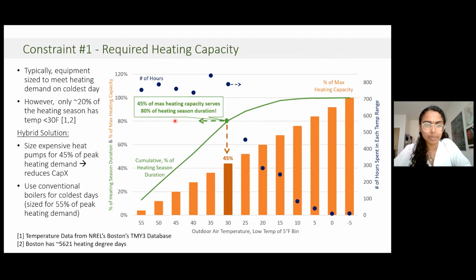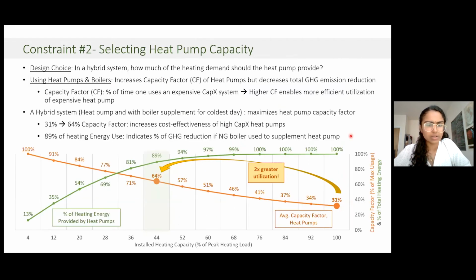And what we would do for the remainder of the heating season is use conventional electric boilers. And these systems, as we mentioned, are less efficient, but are also less expensive. And so what we're able to do here is reduce the capital cost of our total retrofit while maintaining the thermal comfort throughout the year. Another question that you might ask with a hybrid system is, what is the utilization of our heat pump as part of the system? And another question is, what is the expected greenhouse gas emission reduction given that the whole system is not run by heat pumps?